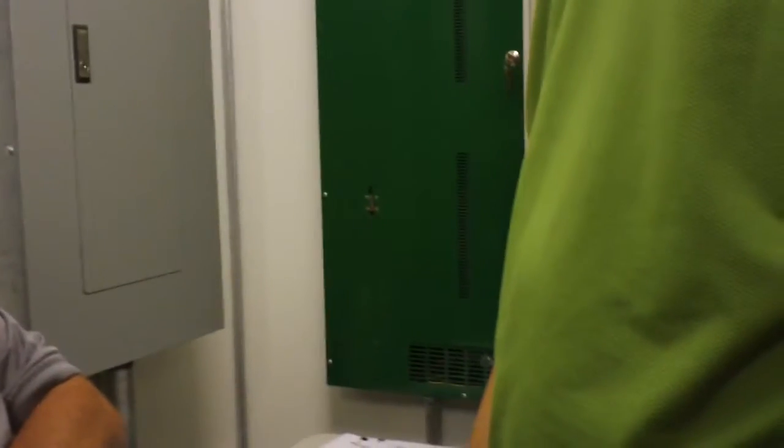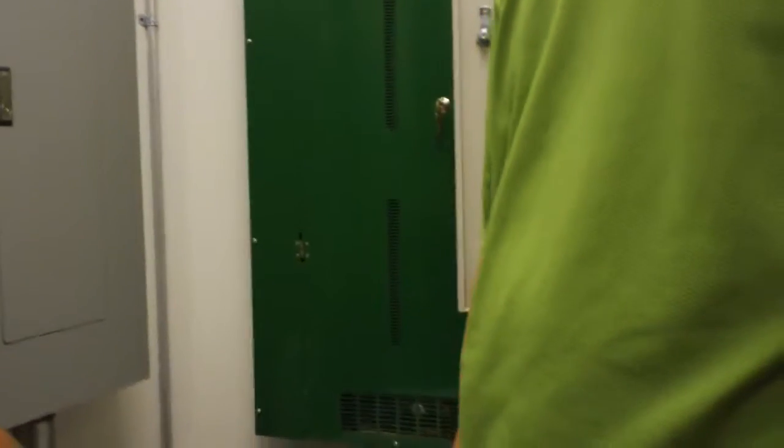He's saying that when he sees the status of the supply fan motor running, low speed fan under 1 amp, and when heating starts up, what do you call it? The little motor, the inducer fan motor kicks on. Then on his system that motor is off, the amp draw is basically 0. On the inducer fan motor? No, on the supply fan motor. So yes, his system thinks that motor is off. That is correct. It is off. Oh, it is off during the induction.